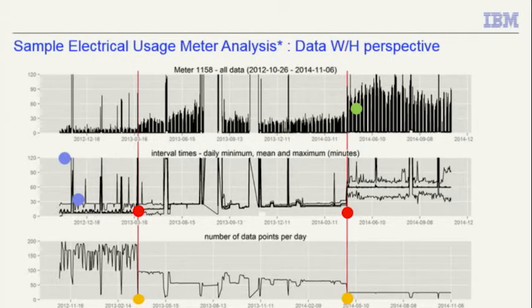The thing about meter data is that you're sampling from one time to the next time and getting the difference. So depending on how that time variance changes, it looks like the consumption is higher or lower. Now you might say, oh, we don't have that problem. I set the system up and I put in 15 minutes. So now when I display anything or put analytics, I'm going to use 15 minutes.